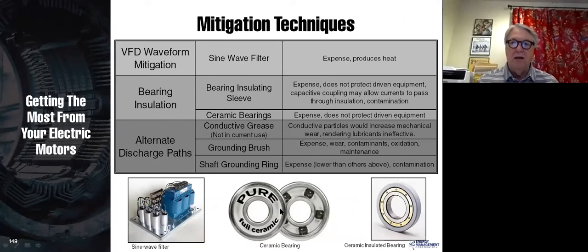Now, the insulated bearing actually has, and this is a full ceramic bearing, the balls are made out of ceramic. I mean, that's incredible. They do have insulated bearings like this where they use a standard bearing and just put an insulated coating over the outside of the bearing to insulate it from the shaft. This in theory works. We have not been totally happy with that way of doing things.